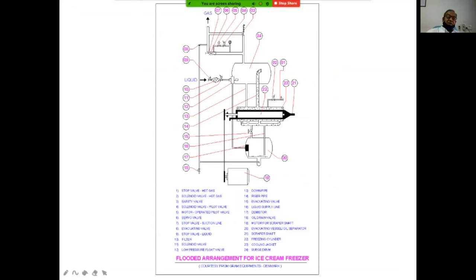How it looks is a flooded system, which has been shown here. This is a flooded system where the refrigerant is put in the cylinder jacket and it is coming out. Generally with ammonia, we use a flooded system. So it will go to the centralized ammonia system. Liquid is coming from the centralized ammonia system here. It is coming here, and this is, you can say, the accumulator or the liquid and gas separator, and liquid is fed and goes here again. And again, suction is taken to the centralized ammonia plant.